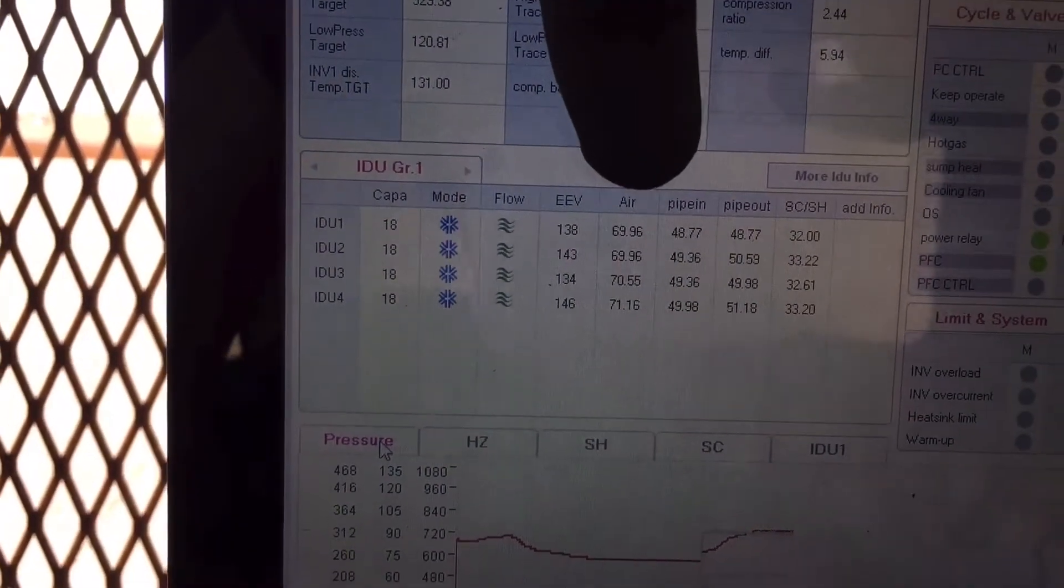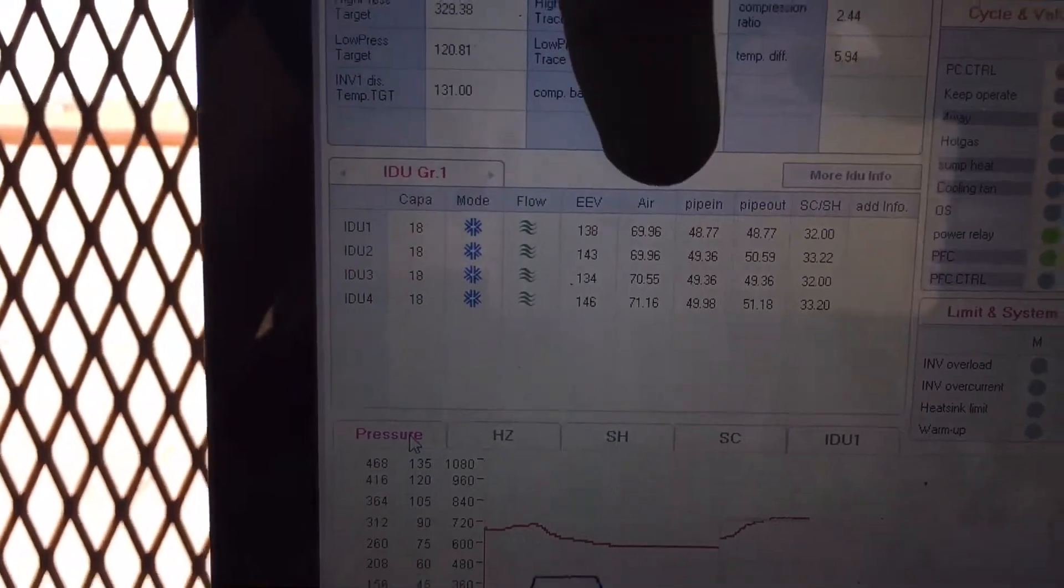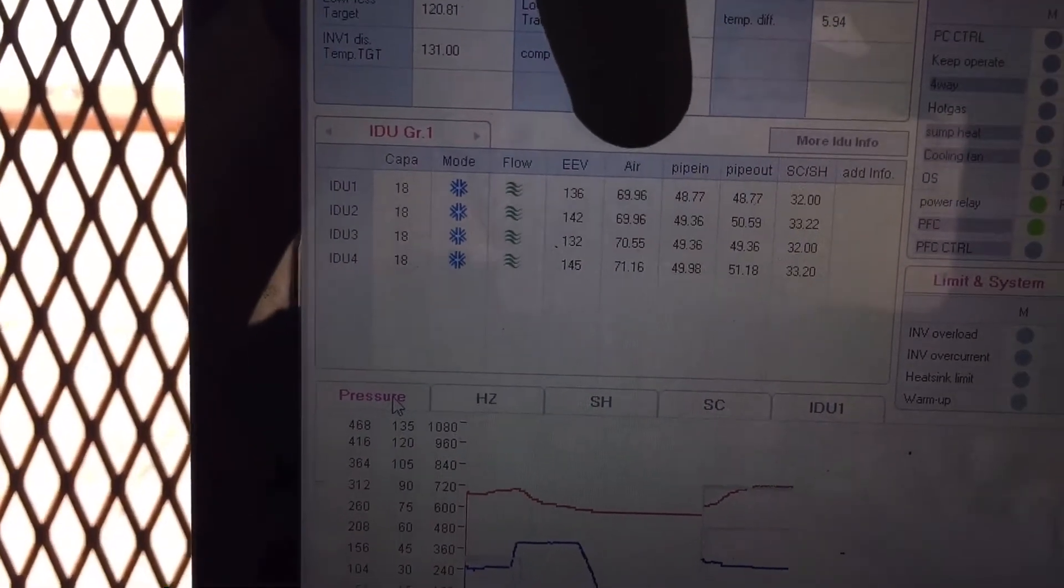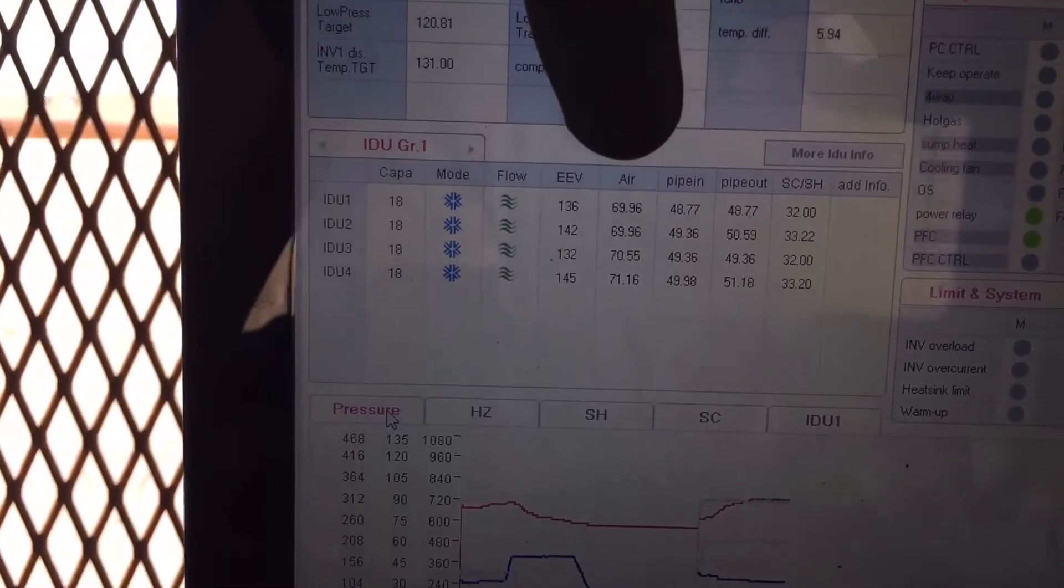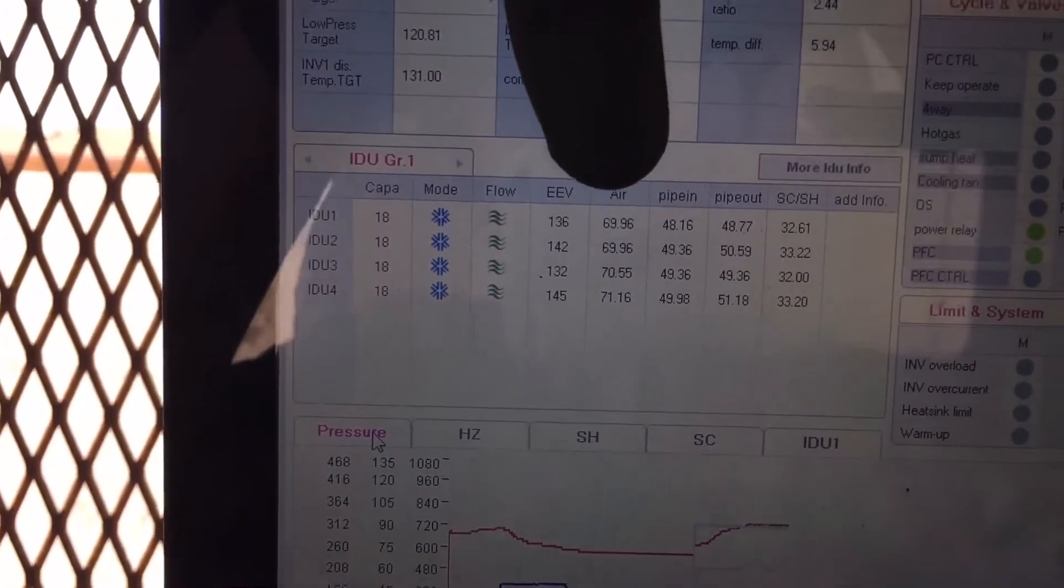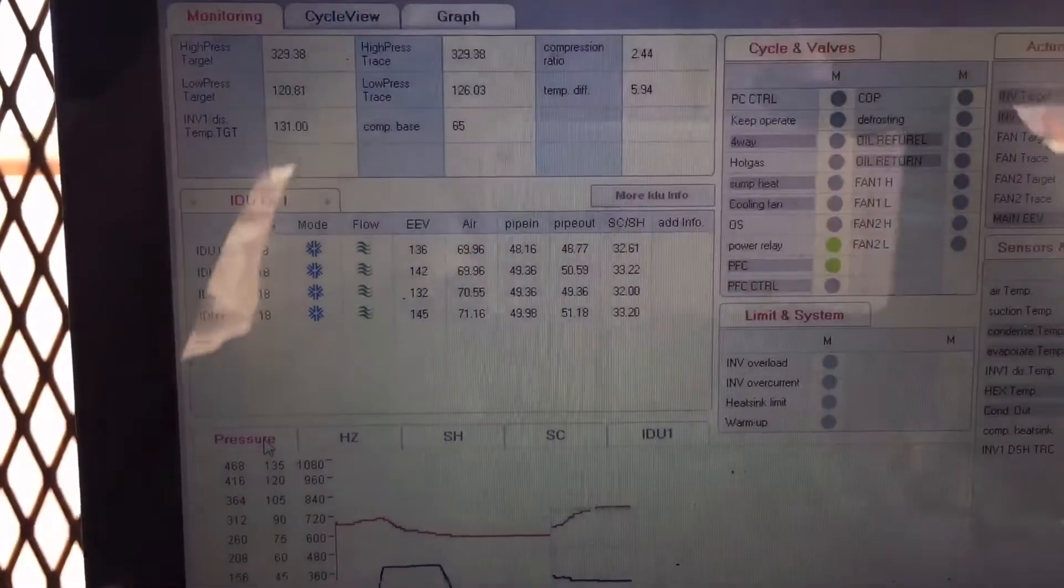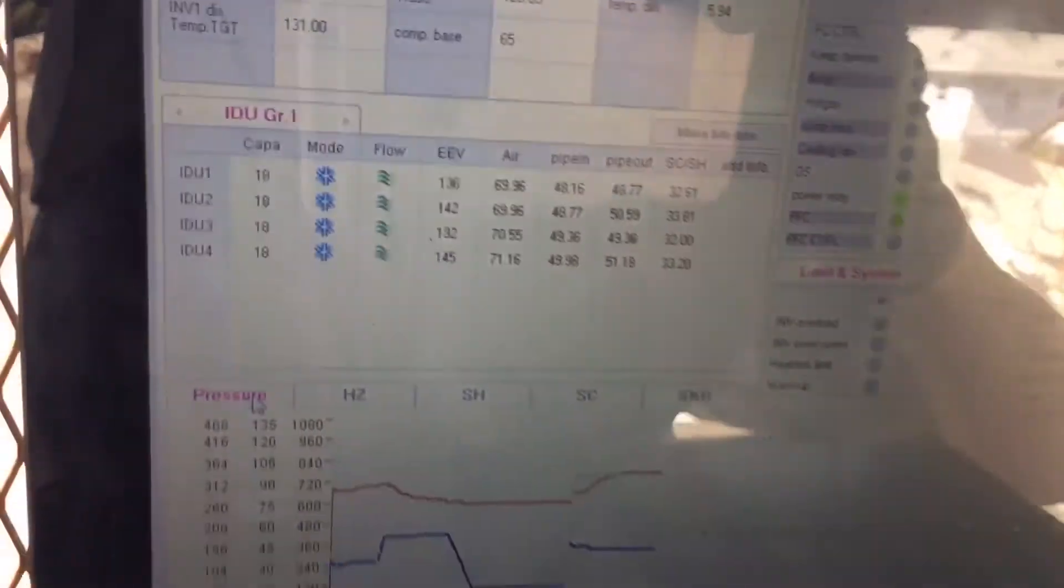Now I just came upstairs, turned the units on while I was downstairs, walked out of the building, up the ladder, across the roof to the back of the building right here. The temperature has already dropped from like 72.5 to 69 and 61 degrees. So right now this thing is running balls to the walls and screaming.